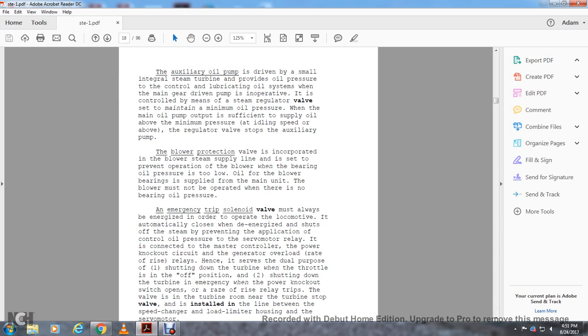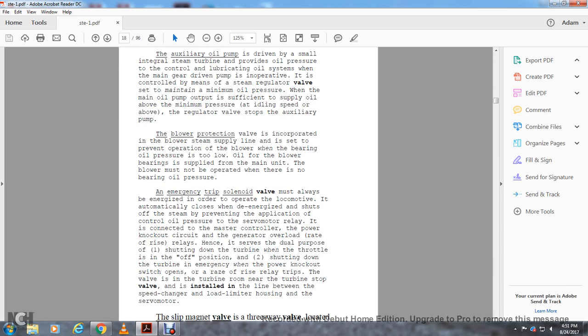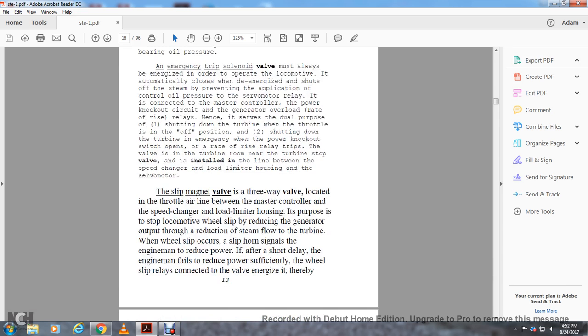Hence, the turbine is shut down in two ways. One, shutting down the turbine with the throttle in the off position. Two, shutting down the turbine in an emergency with the power knockout switch, which opens a rate of rise relay trip for the valve of the turbine room near the turbine stop valve, inside of the line between the speed changer and load limiter housing and the servo motor. The slip magnet is a three-way valve located in the throttle air line between the master control speed changer and the load limiter housing.